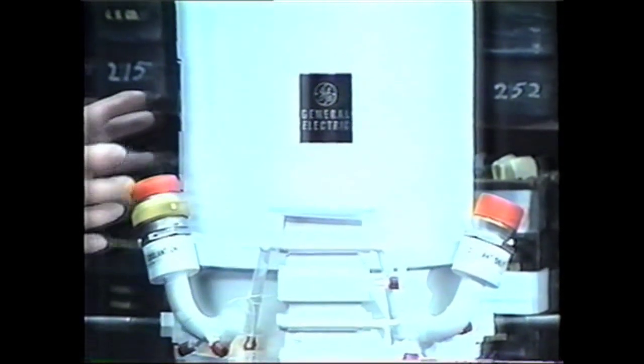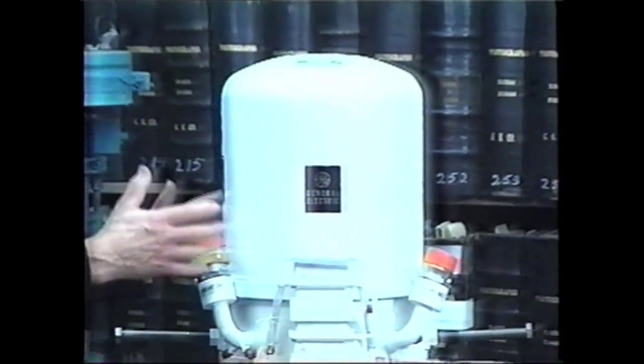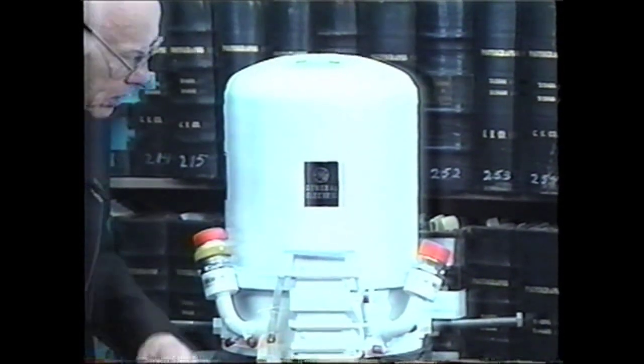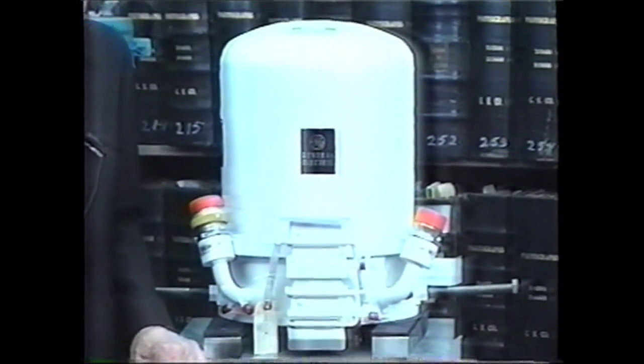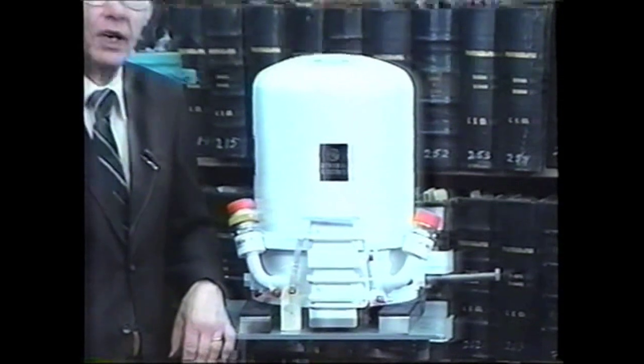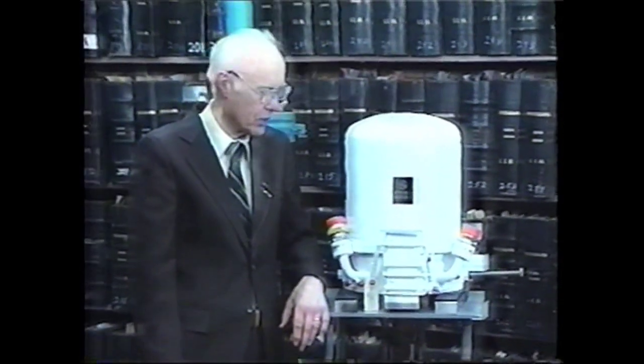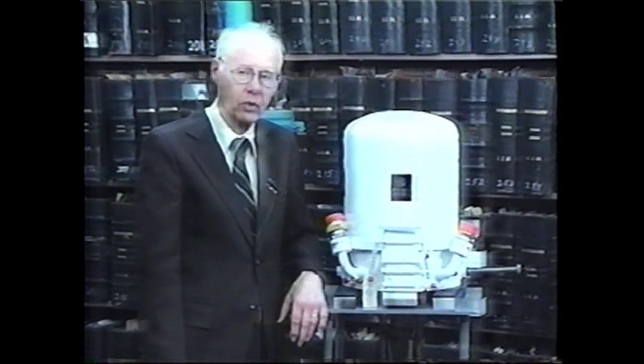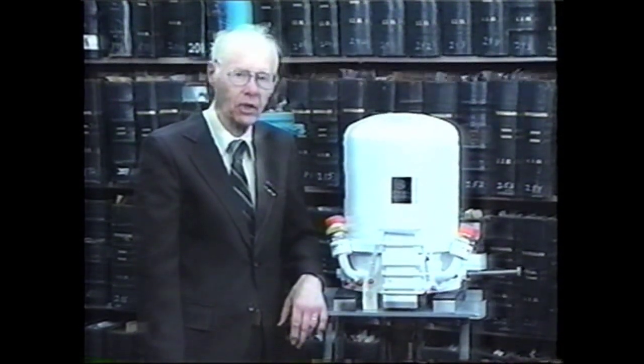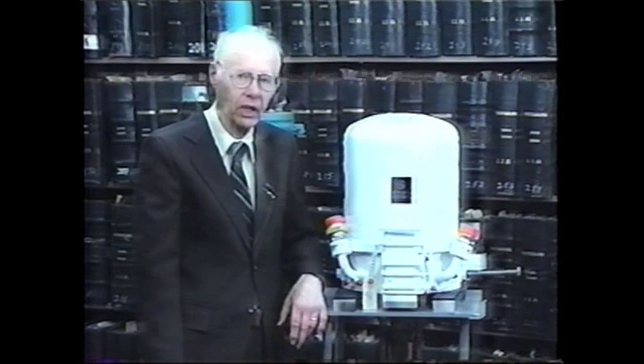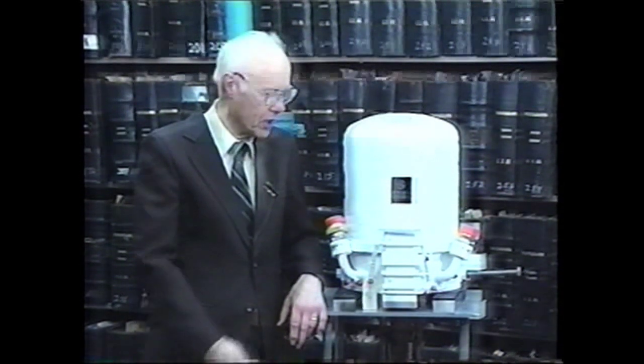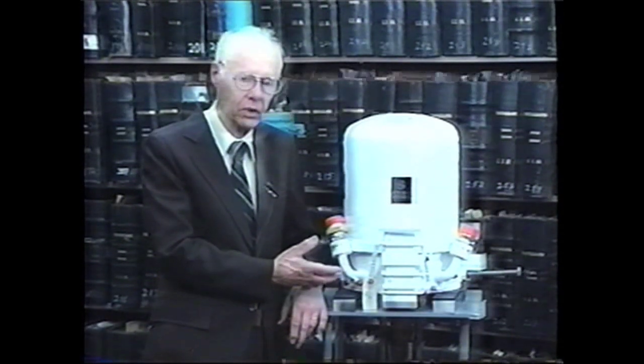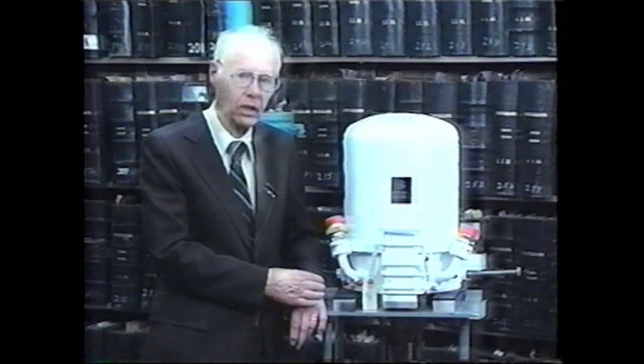The collector is a very large box here, again, water cooled. And power output of 1 megawatt of peak power. Average power is, again, in this case, in the order of 5 kilowatts. This tube was made in large quantity, applied to all of the radar systems. General Electric remained the sole supplier of that tube until it decided to quit the business in the end of the 1970s. So this represents the combination of a lot of technology know-how and design know-how, largely obtained by means of modeling, and is about where the state of the art in klystrons is as of 1990.